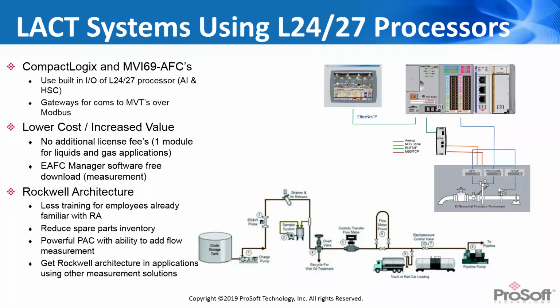It allows a lower cost and basically the license-free model of the flow computer. One of the key things when we started working with producers is that you don't necessarily want your measurement team requiring a license for Studio 5000 or RSLogix 5000 and becoming a PLC programmer to make changes. So we provide a free EAFC Manager software that can be used to change things such as a meter factor of a Coriolis meter, or to perform functions like transmitter calibration of a multivariable transmitter on your site. And for customers that are already familiar with the Rockwell architecture, it allows you to have less training, reduce your spare parts inventory, and really allows you to use Rockwell architecture in some measurement-related applications that you weren't able to do before.